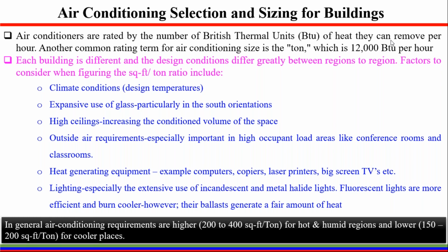Incandescent bulbs are being phased out, but they are still being used in most of the SAARC countries. Those bulbs generate a lot of heat, and when we choose the air conditioning, we can replace these bulbs with more efficient bulbs that don't produce much heat. But every light produces heat, and we have to take care of that heat when we size our air conditioning systems. In general, air conditioning requirements are higher for hot and humid regions and lower in cooler places.